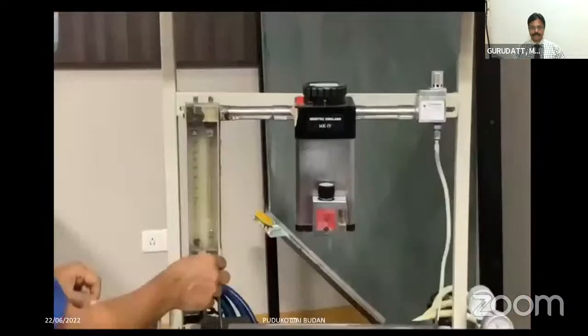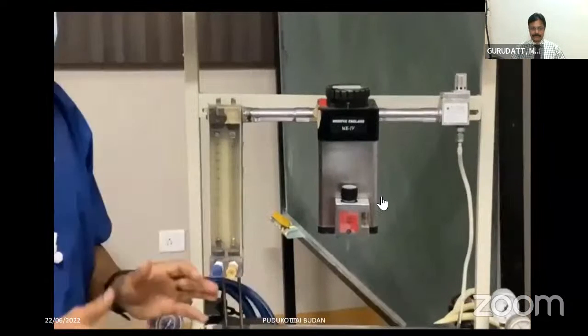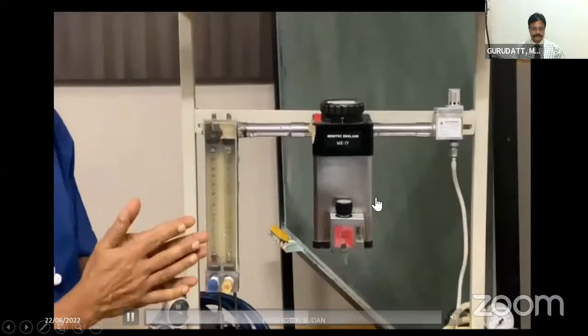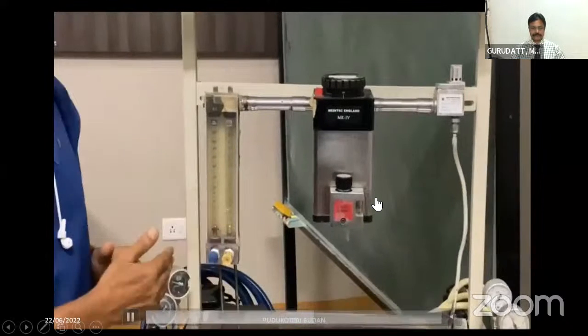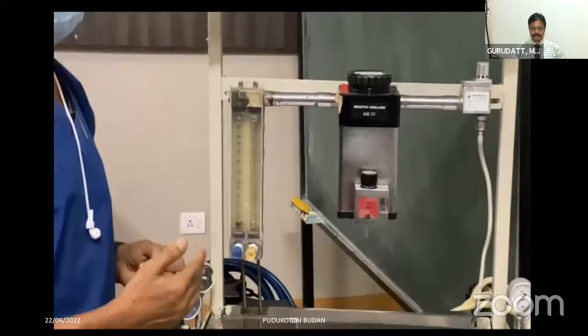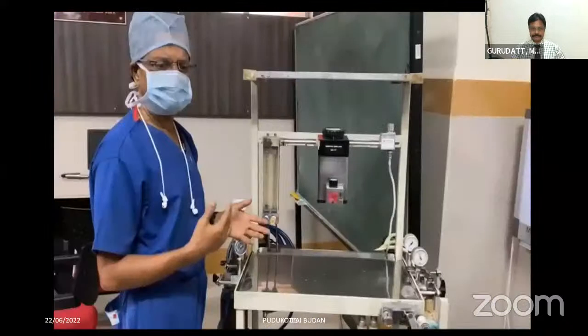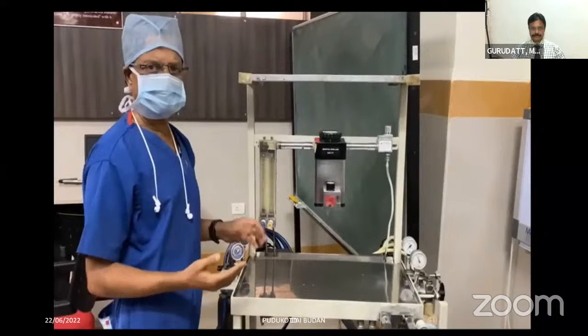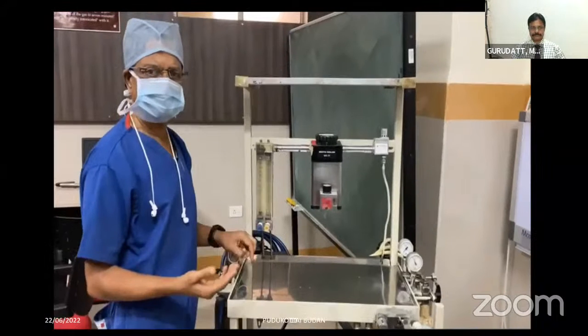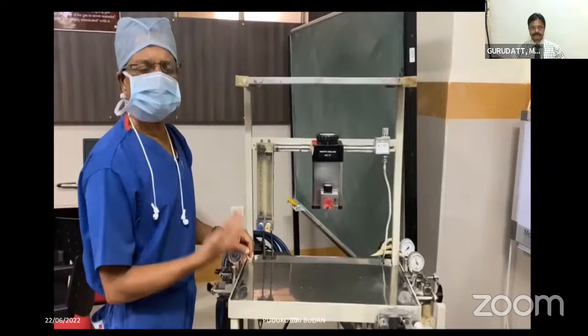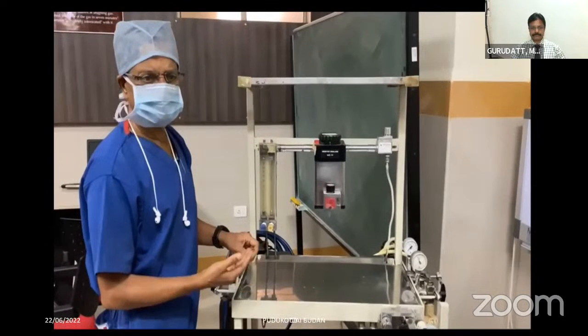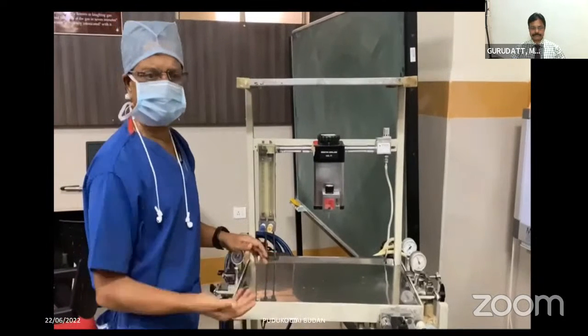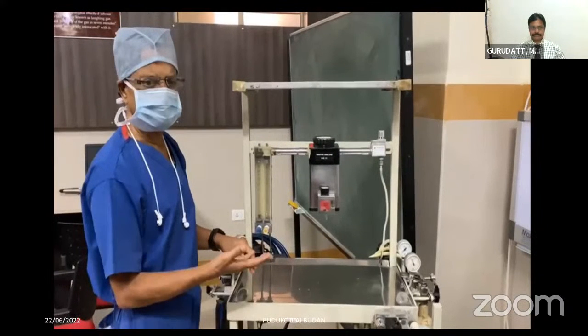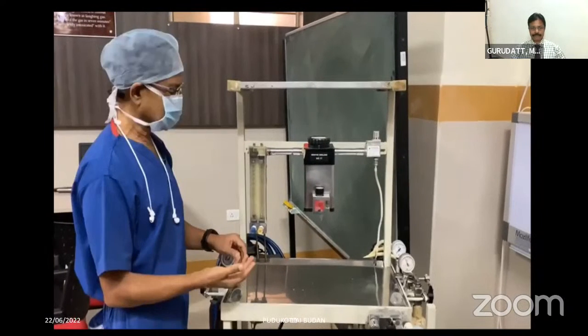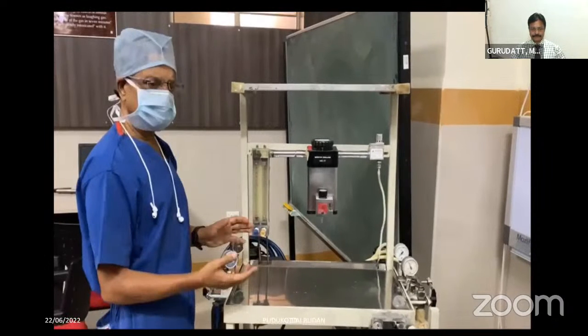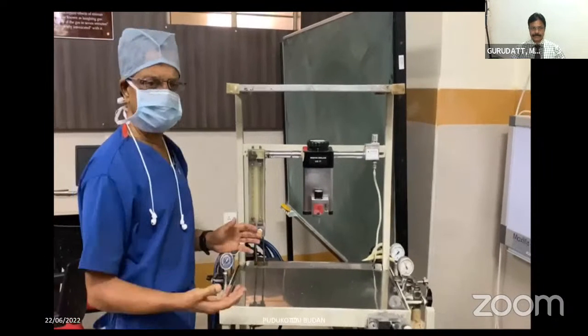So once I have opened oxygen, there is the problem with the fail-safe systems, or the pressure slave regulator system, of the older machine and also the fail-safe valves of the newer workstations. In the newer workstations, we have fail-safe valves which have replaced the master-slave mechanism that was there in the older machine. These are also almost like master-slave only. The oxygen pressure has to be there to open the fail-safe valve of the nitrous oxide. So though they are called fail-safe valves, they are not actually fail-safe.